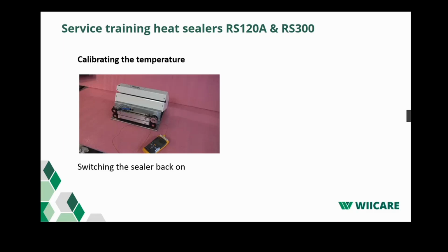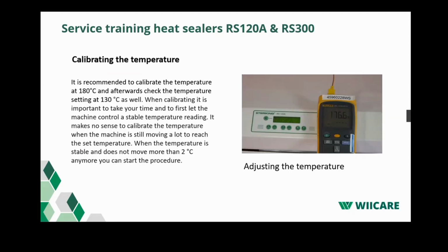Now we're getting to the next video, and that's explaining how to calibrate the temperature within the machine. Connect the power supply and switch on the sealer. Let the sealer heat up first. Okay, this is the actual video which I just wanted to say. That's how to calibrate the actual temperature in the machine.